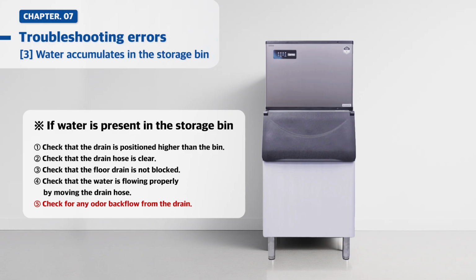Occasionally, odors from the drain may flow back through the drain hose. Install a check valve or keep the drain hose as short and straight as possible while maintaining a downward slope toward the floor drain. Regularly clean the drain using a cleaning agent or deodorizing solution to prevent odor buildup.